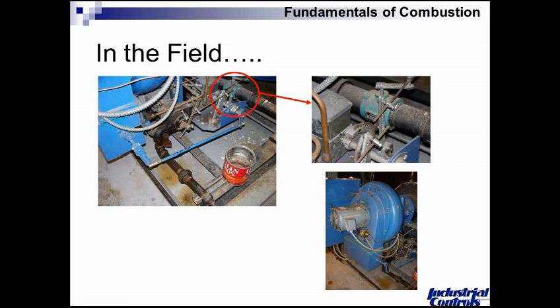This is ultimately where the fuel-air ratio is dictated on this particular boiler. Just as an observation, industrial facilities and boiler rooms aren't always the cleanest places in the world. When I look at all those cams and shafts and springs, I see lots of potential for things to just not stay consistently what you want.